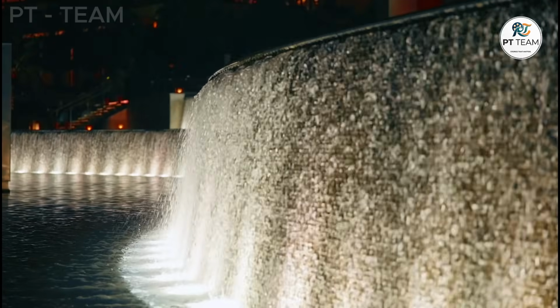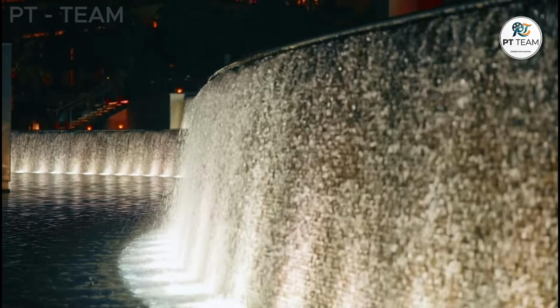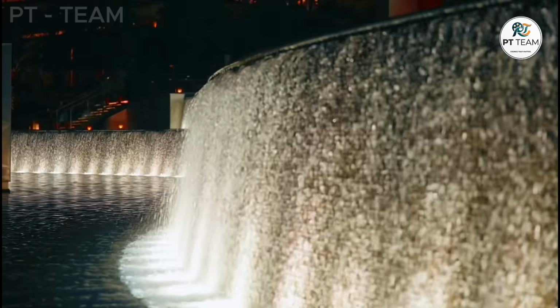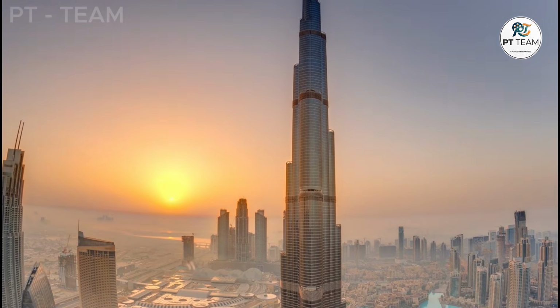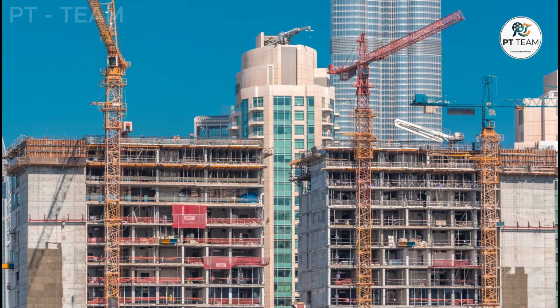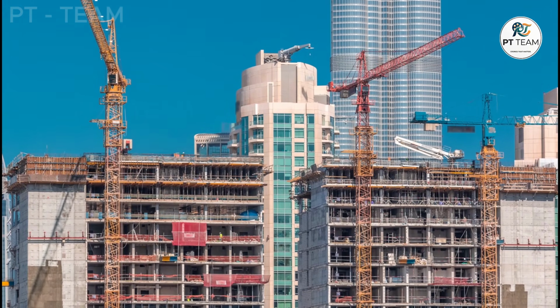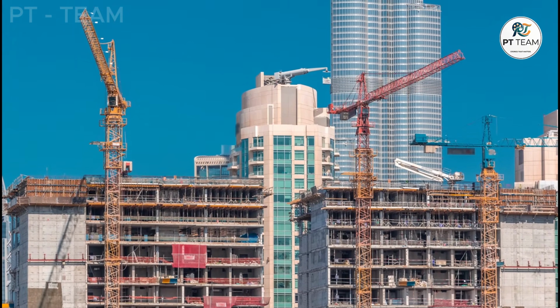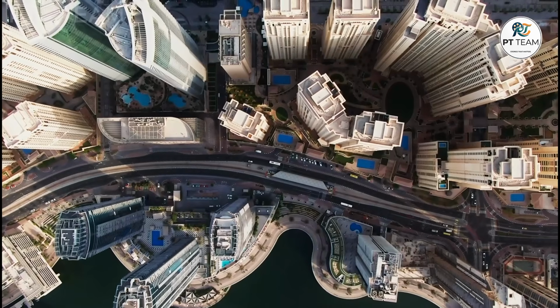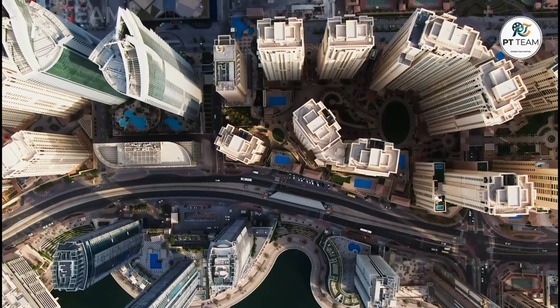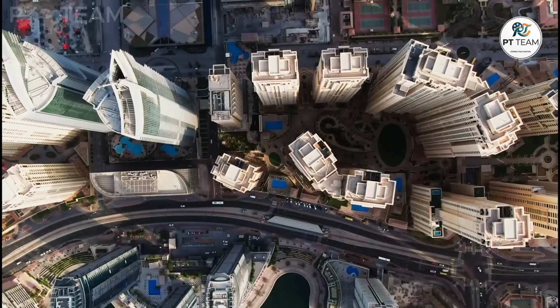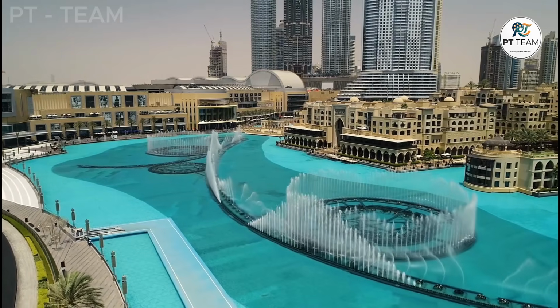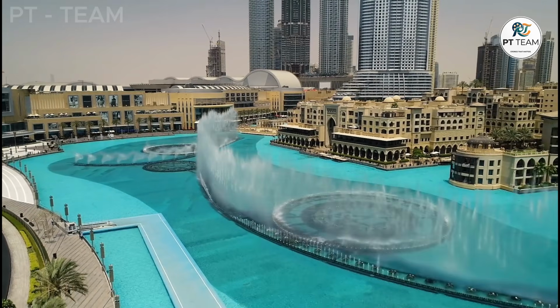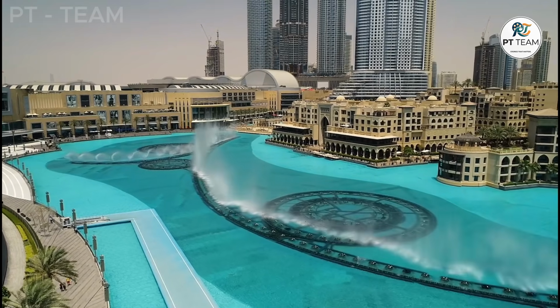But the most critical interventions must happen before the mechanical cooling is even required. Future development must reduce unnecessary solar gain by designing facades intended for an actual desert climate, rather than a temperate zone. This means drastically reducing unnecessary structural glazing on sun-facing elevations. It requires improving building insulation and ensuring tight thermal envelopes to prevent cold air from escaping.